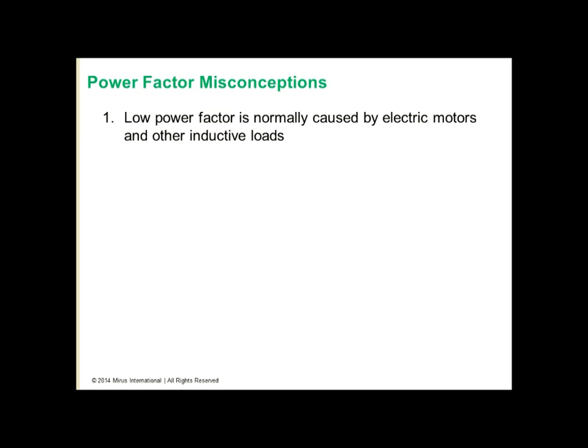So the first power factor misconception is that low power factor is normally caused by electric motors and other inductive loads. Although it is true that inductive loads consume reactive power and thereby reduce power factor, with today's proliferation of harmonic generating power electronic nonlinear loads, low power factor is now most often due to harmonics. Second misconception is that low power factor can always be corrected by adding capacitance. If low power factor is due to harmonics, treating with capacitors can often make the problem worse.